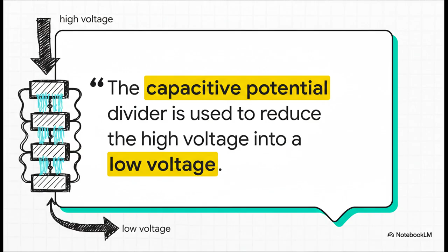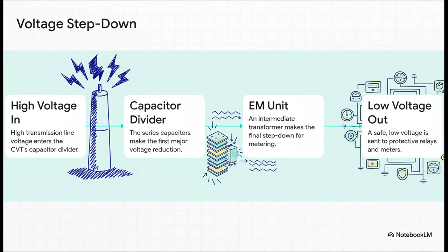Here's how that process plays out step by step. First, that really high voltage, say 400,000 volts from the power line, enters the top of the CVT. Next, the capacitor divider does the heavy lifting, dropping it way down to a more reasonable 10,000 volts. Finally, a smaller electromagnetic unit does one last, precise step down to a standard level like 110 volts, which is perfectly safe for our meters to read.